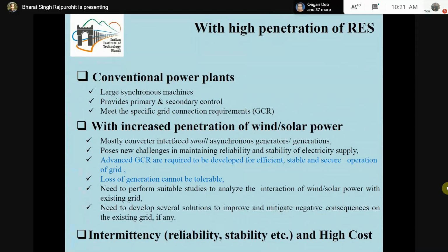wind generators lying there, having a capacity from a few hundred kilowatts to a few megawatts. And then there are solar farms, where a large number of solar PV plants are connected in series and parallel fashion to make up a very big solar farm. So controlling such thousands of wind generators or solar PV panels is one of the key issues to be addressed. That's why we need to address grid connection requirements, sometimes known as grid codes, which are given by the Central Electricity Authority, which need to be achieved.